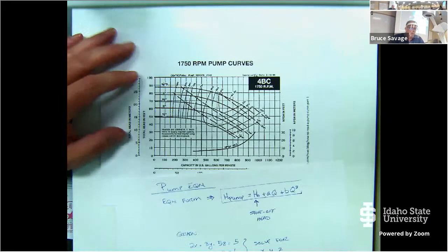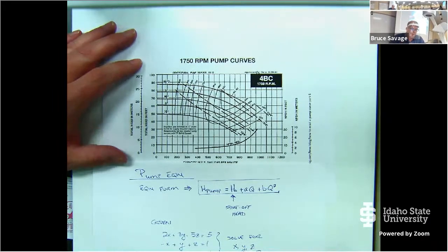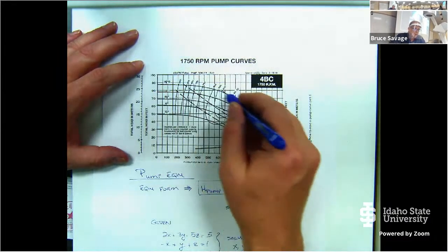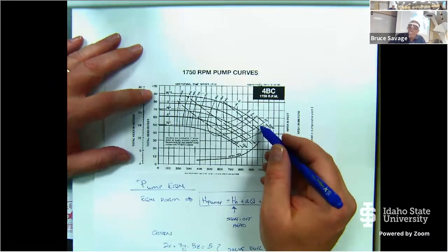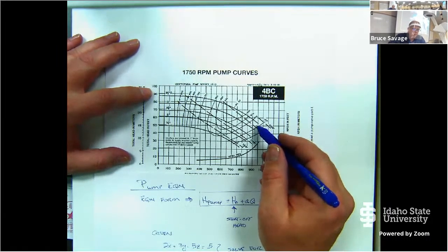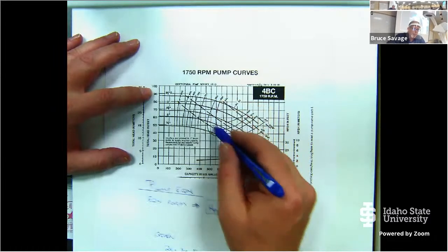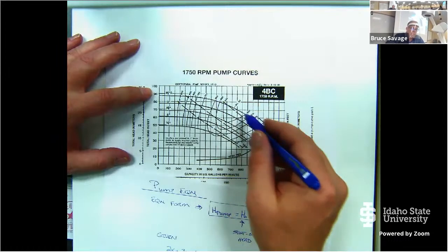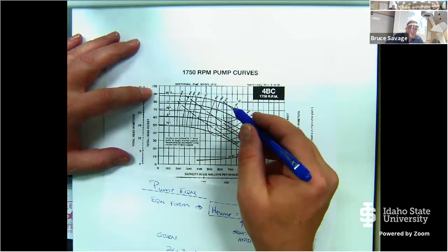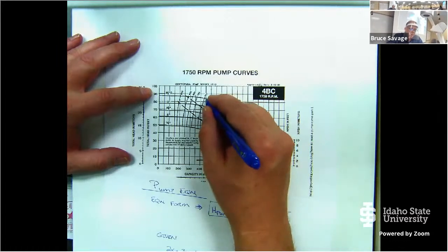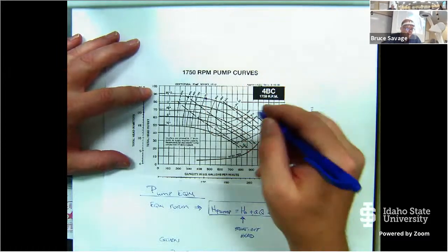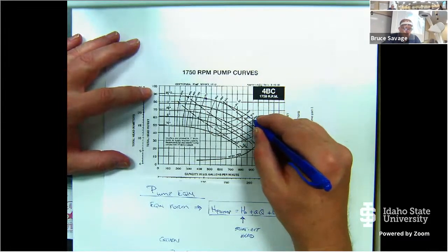Then, as an example, let's say I wanted the pump curve for the highest one up here, that 9.5 diameter pump. I think I'm going to try and operate out in this region where it's the highest efficiency, so I'm going to pick some points that capture that best. I'm going to come over here and pick 450, put a little dot right there, and then come down here and pick 900, since those are right on.